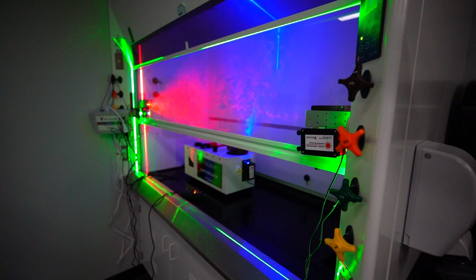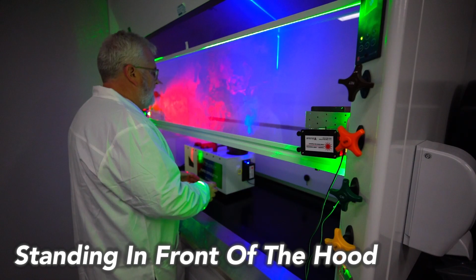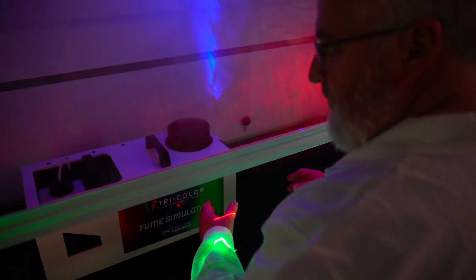A person standing in front of the hood creates turbulence that can draw chemicals out of the hood. So all you want to do for this challenge is walk right up to the hood and just stand there. The fume hood is pulling in air from behind you. So when the air goes around you, it can create a low pressure zone right in front of you. That can cause reverse flow and pull chemicals out of the hood. So you want to be watching directly in front of you to see if any green loss of containment comes from you standing in front of the hood.